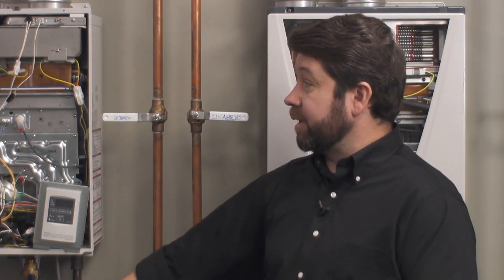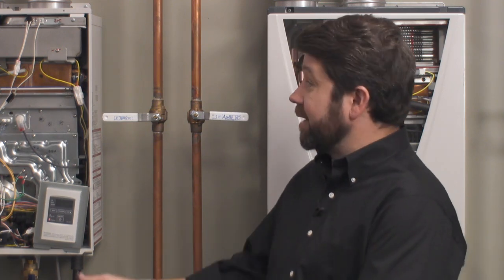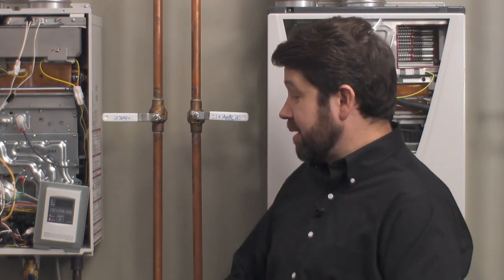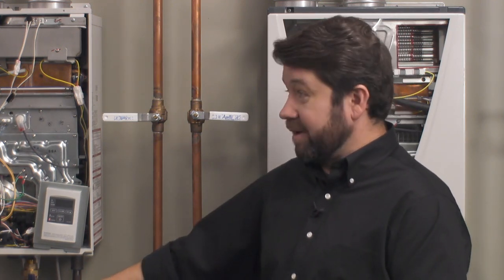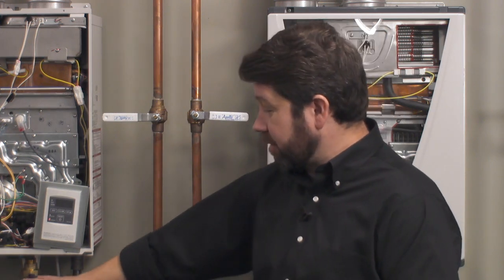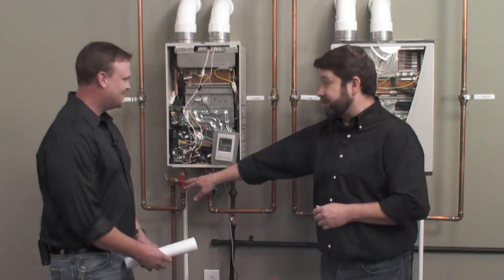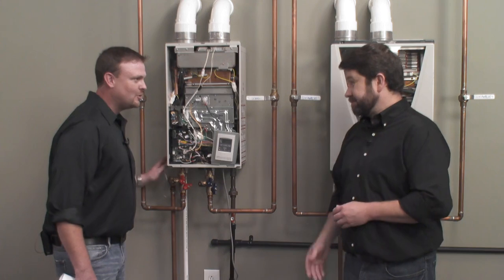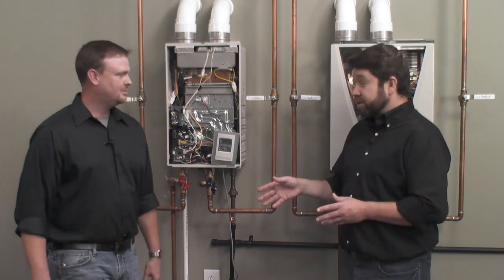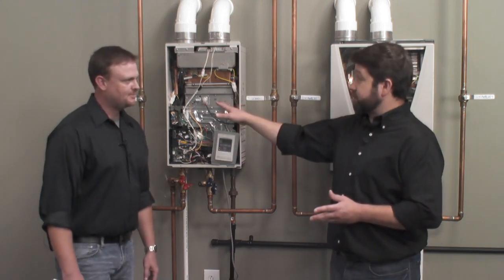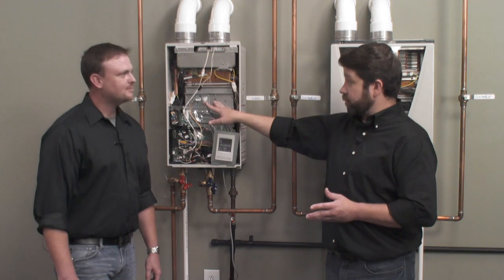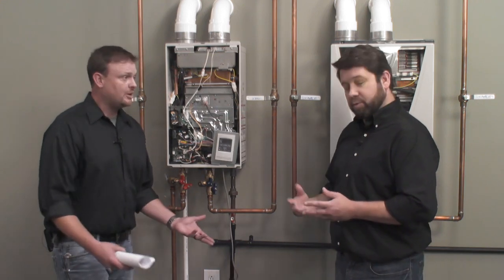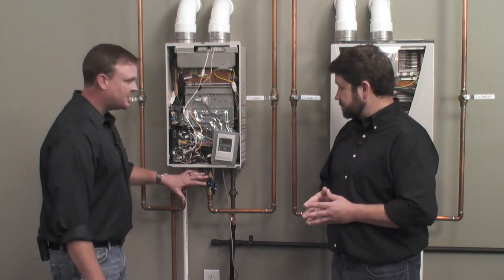Now, if you don't use the isolation kits, in our manual we're still going to recommend that you have isolation valves and you're just going to pipe those in. This saves you from doing some pipe fitting and some sweating. It's all convenient right there. We've got a spot for our pressure-only relief valve. And a pressure only, no temperature and pressure? No temperature and pressure, pressure only, because we're regulating the temperature on demand as we're going through the heater. We're not storing any water either. Okay, so an isolation kit is a must.